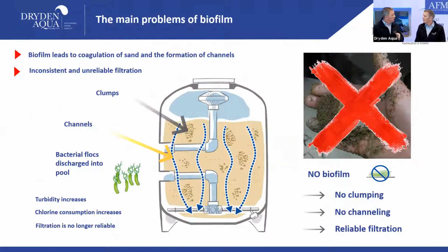May I add a few points? Sure. Excellently explained. This wormhole channeling, maybe it's only open for 15 minutes or maybe a day. After a backwash it will close, but then it can form again. And if you have this channeling, as you said, it's not reliable anymore. You get this bacterial flocs through.